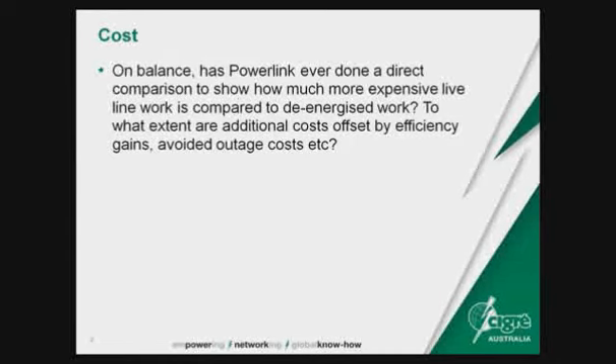From Powerlink's point of view, one area we look at is disconnector maintenance. Our budgets are set the same for live substation work as for de-energised work. This works out because with the layouts of our switch yards, most of our disconnectors that are maintained live are done in such a way that it's not necessary to shunt. In this scenario, it's actually quicker and cheaper to do it live.